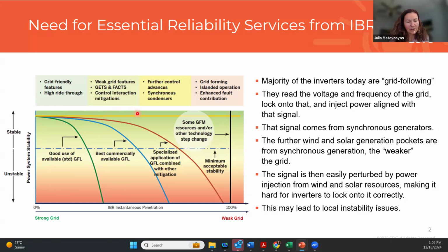As we progress towards maybe 30-40% penetration of inverter-based resources, even more requirements are being put on inverter-based resources themselves. So there are so-called weak grid features, where inverter-based resources are required to behave more stably in weak grid conditions. Control interaction mitigations, maybe some additional devices are being added on the grid to maintain stability. As we move towards even higher shares of inverter-based resources, maybe like 70% or 75%, then even further control advancements are needed from grid following inverter-based resources, but also now system operators start looking at synchronous condensers. So a synchronous condenser is a synchronous machine without a prime mover. So it has some of the capabilities of a synchronous generator without injecting megawatts into the grid.